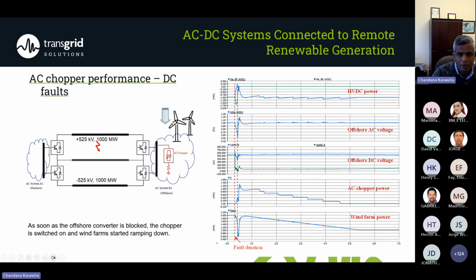You can actually ramp down the power and operate the AC chopper in such a way that you keep the power balance while the wind farms are ramping down. You can see here the wind farms ramping down the power to the level that we want, and the chopper keeps absorbing the excess energy of the system. You can coordinate these systems together, so we don't have to trip the wind farms. The wind farms are still operated, but at a lower power level. As soon as the HVDC comes back, we can ramp up the wind farms and transfer the power. When we have a parallel AC connection, it's even easier.